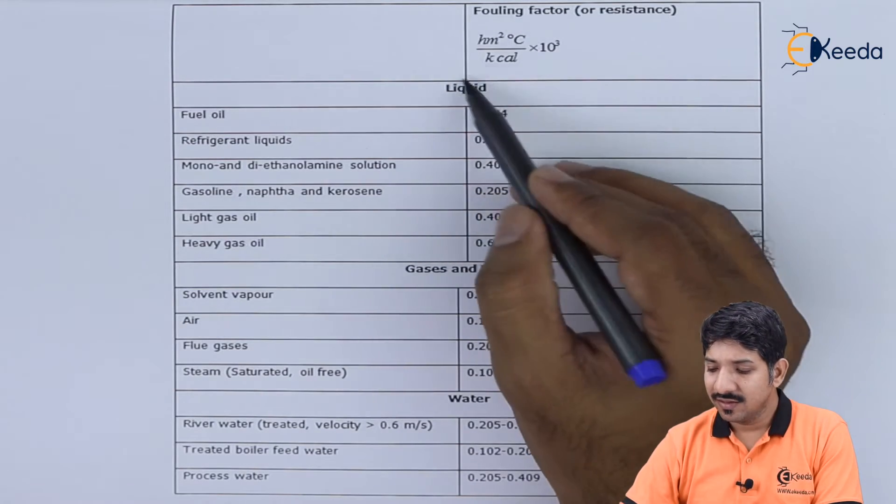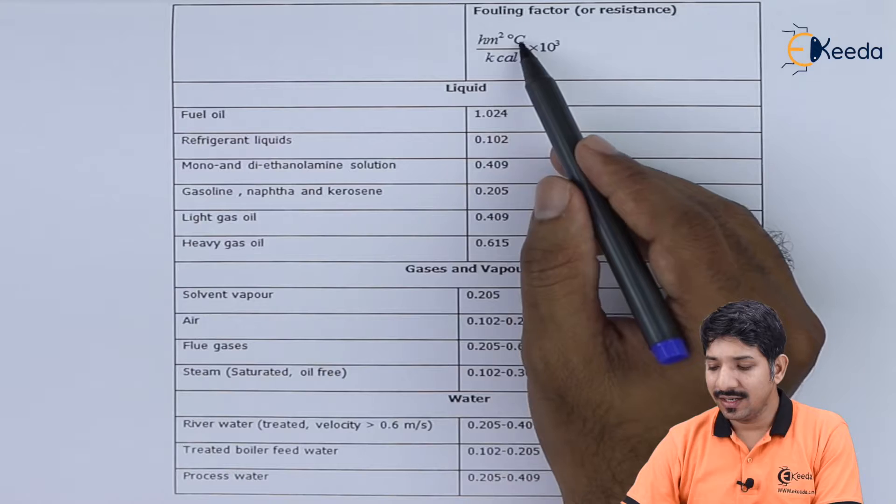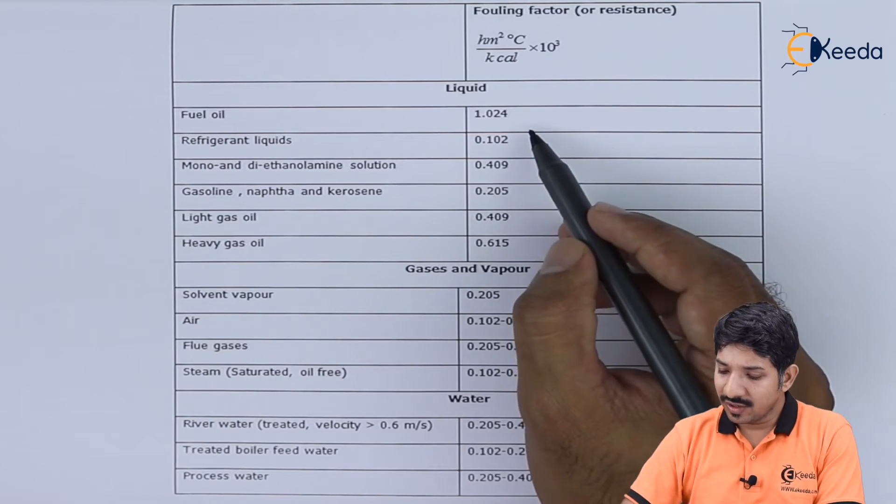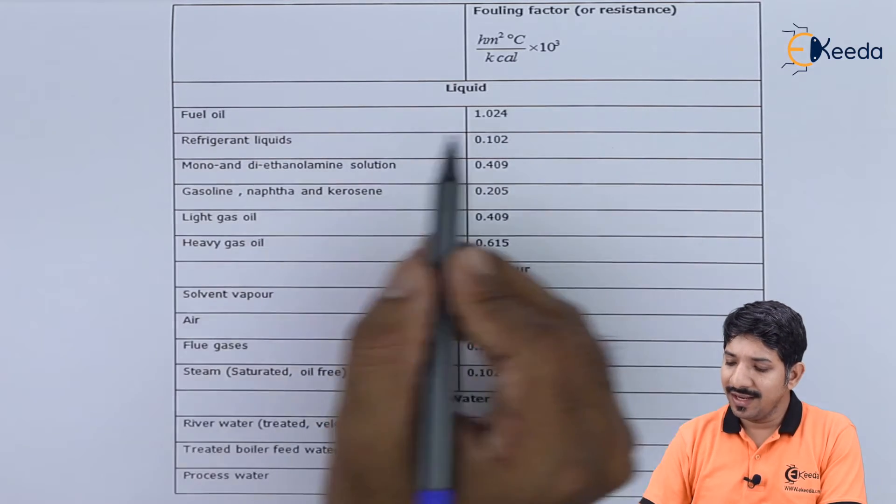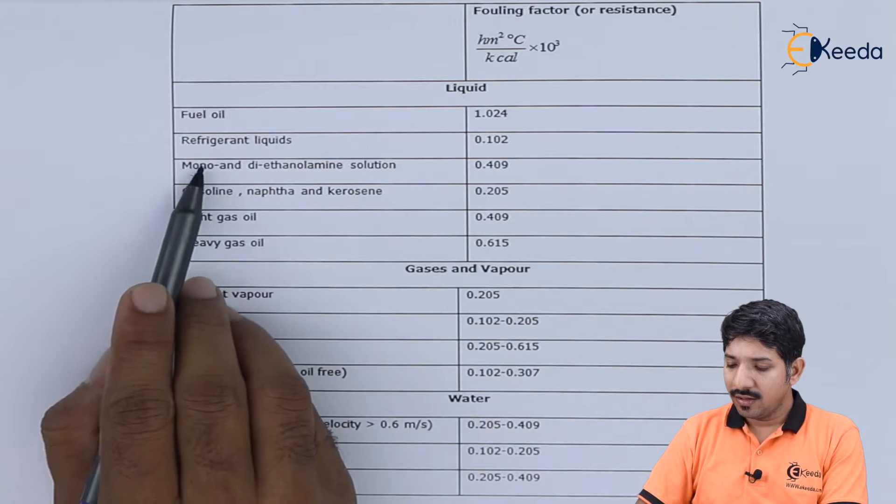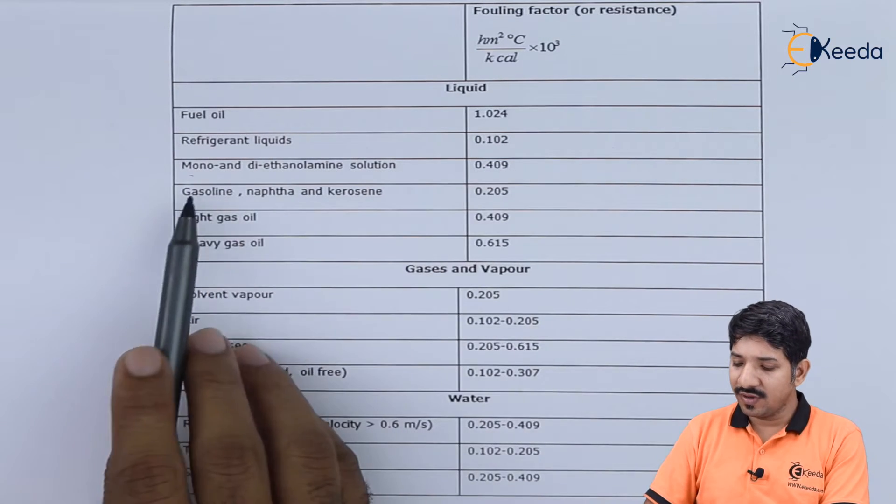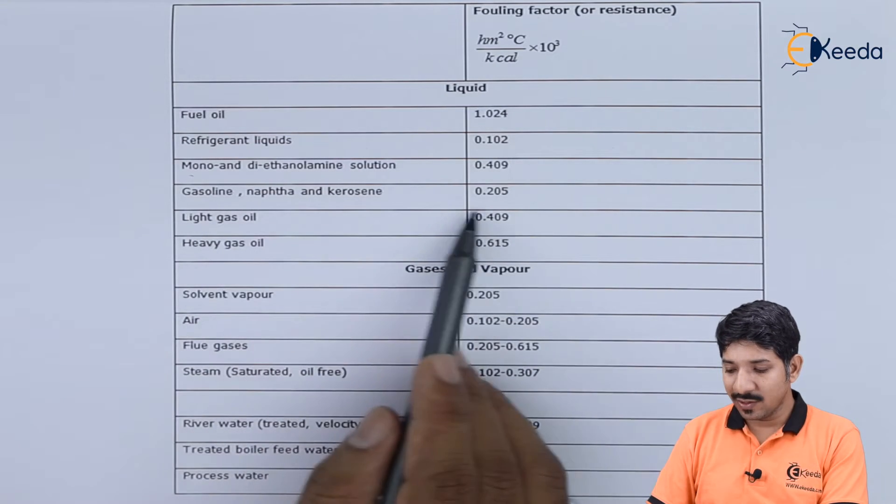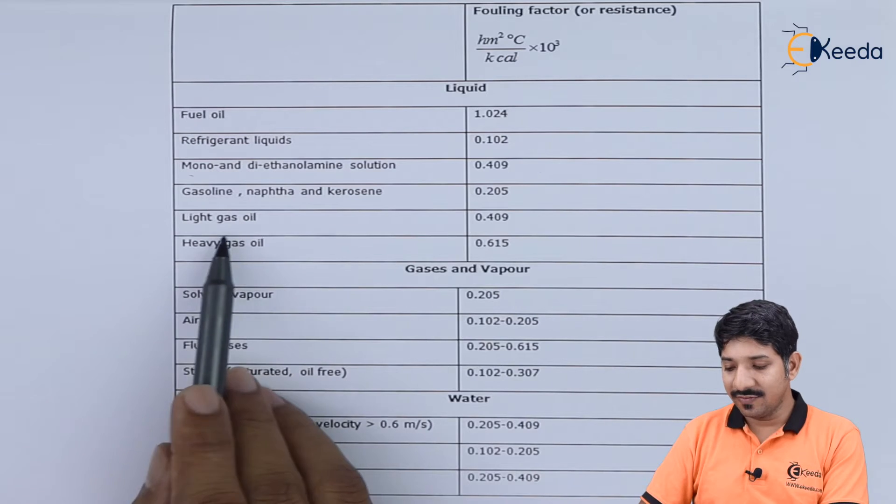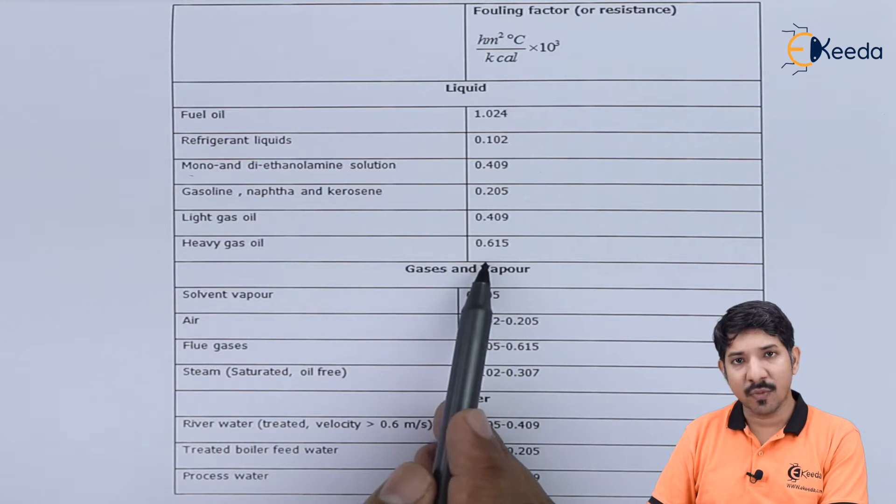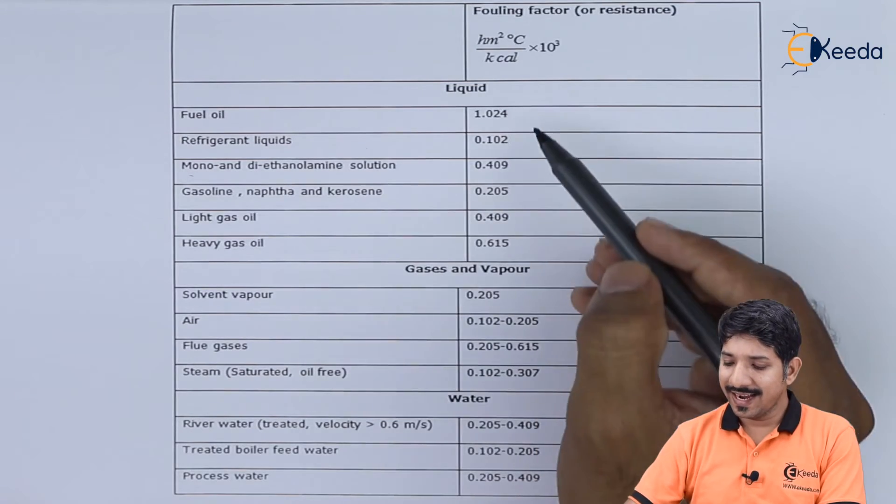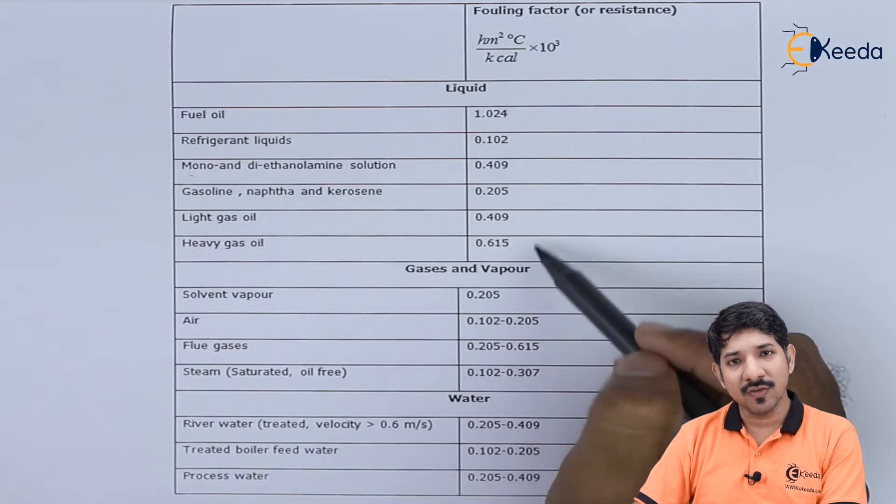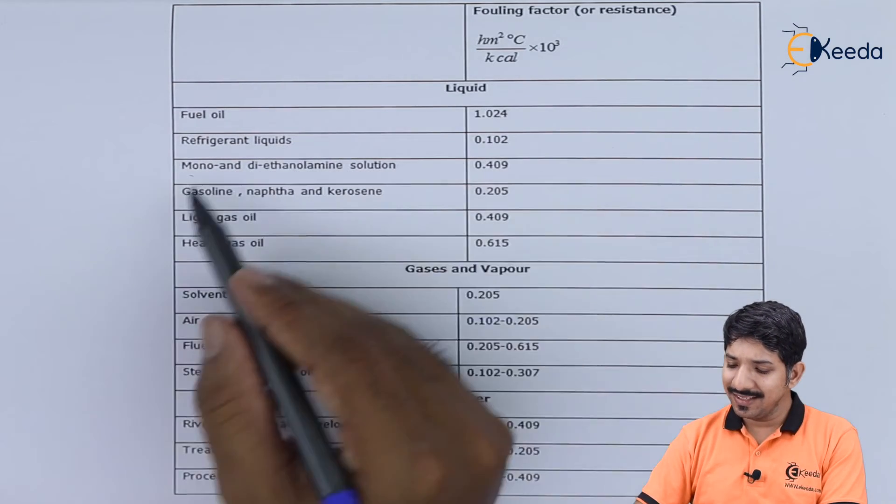This is given for understanding the quantity of the fouling factor. The unit is hour × meter squared × degree Celsius per kilocalorie. For fuel oil it is 1.024, for refrigerant liquid about 0.1, diethanol solution 0.4, gasoline or kerosene 0.2, light gas oil 0.4, and heavy gas oil 0.6. Only for fuel oil it is more than 1; for the rest it varies from 0.1 to 0.6.